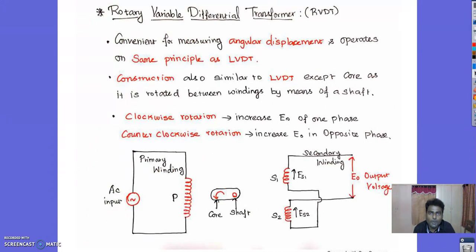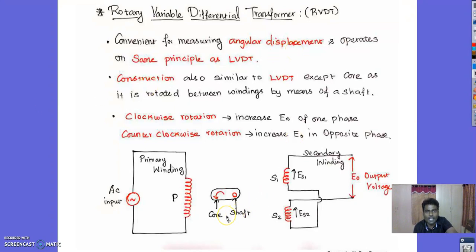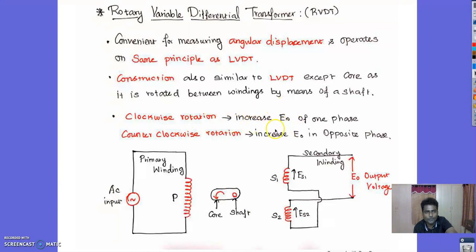Next is the Rotary Variable Differential Transformer (RVDT). The construction is different but the operating principle is the same as the LVDT. It is used for measuring angular displacement, whereas LVDT measures linear displacement. The construction is similar to LVDT except the core rotates between the windings. When the core rotates in the clockwise direction, the output EMF of one phase increases; when rotating counter-clockwise, the output voltage increases in the opposite phase.